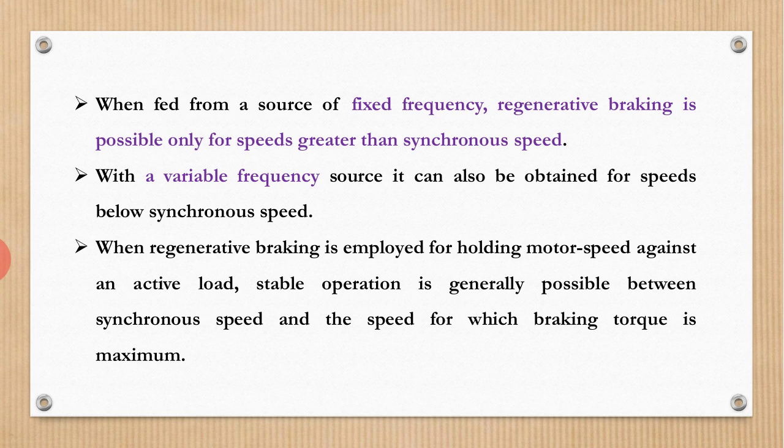The third point is, when regenerative braking is employed for holding motor speed against any active load, stable operation is generally possible between synchronous speed and the speed for which braking torque is maximum.